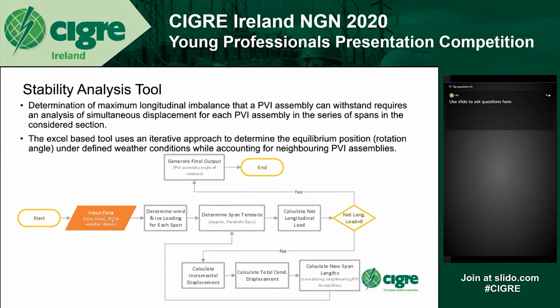We start by inputting the data on the line design, conductor properties, PVI design, and the desired weather conditions. From this input data, the tool calculates the wind and ice loading on each span and determines the associated span tensions.